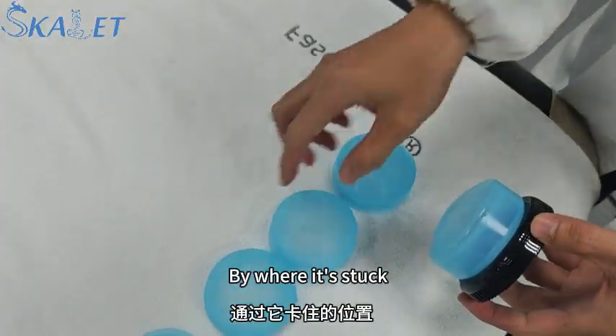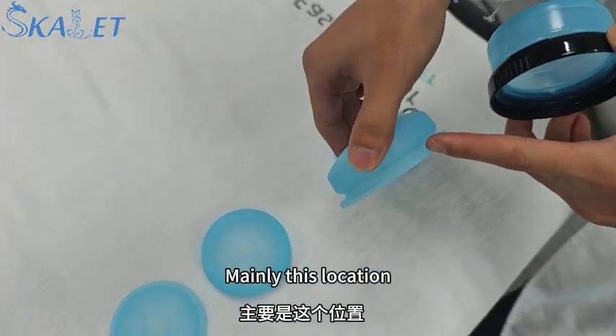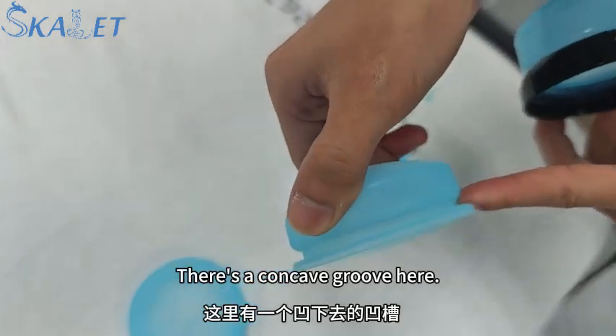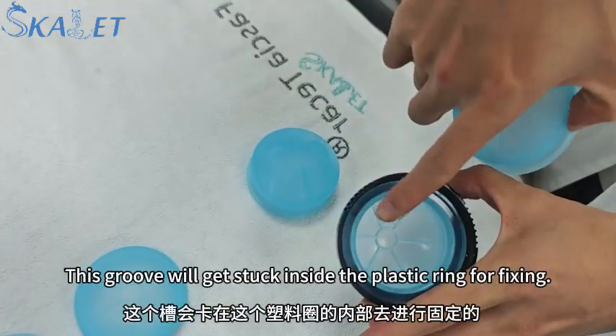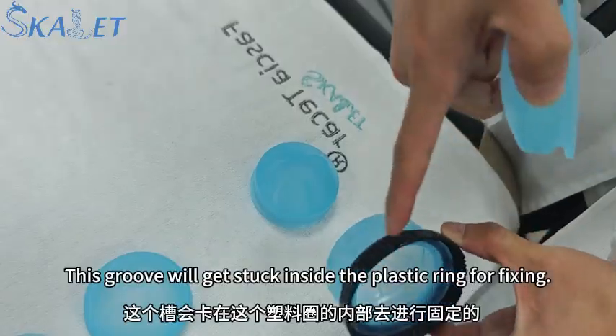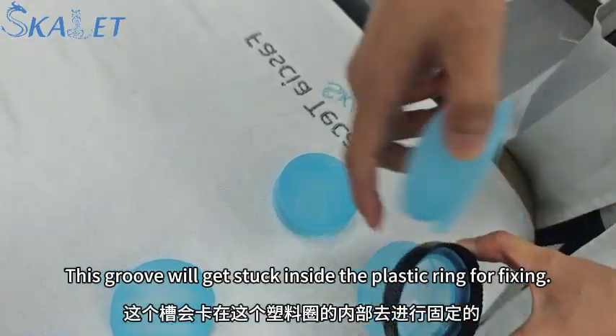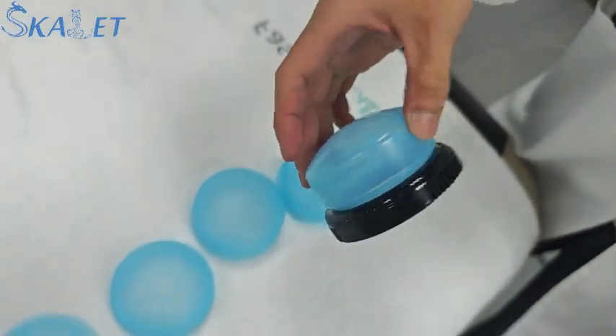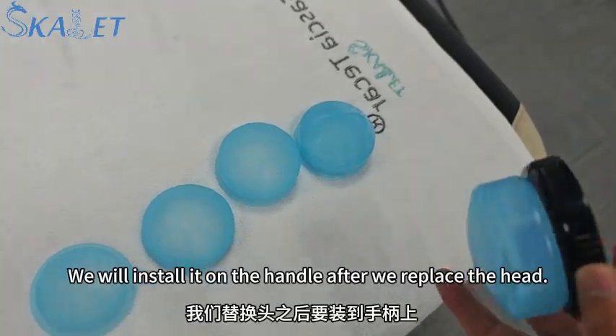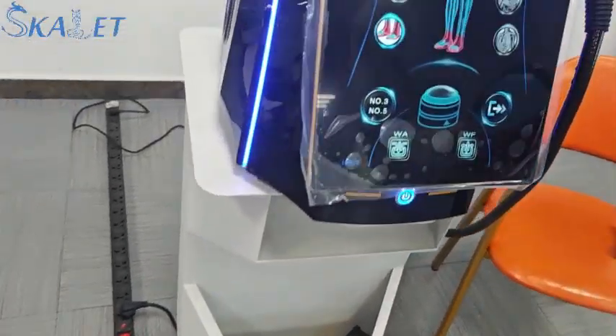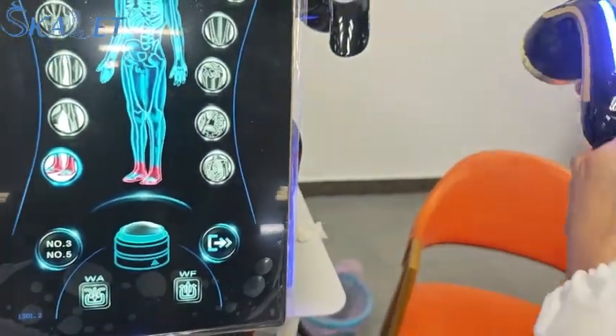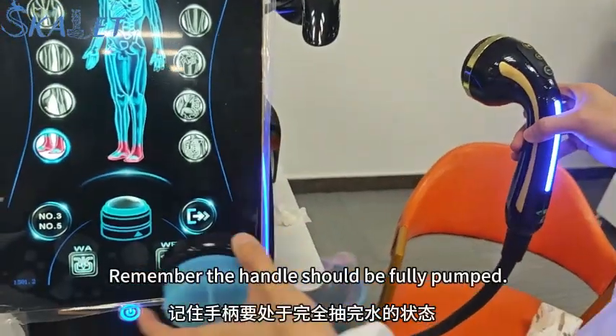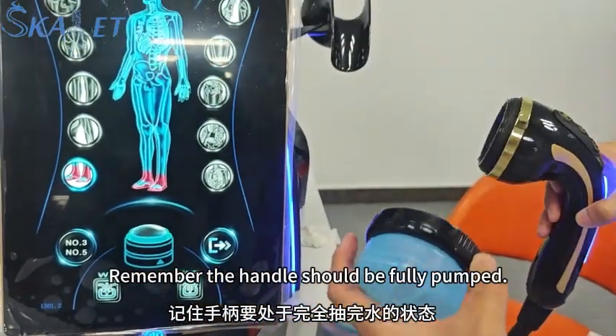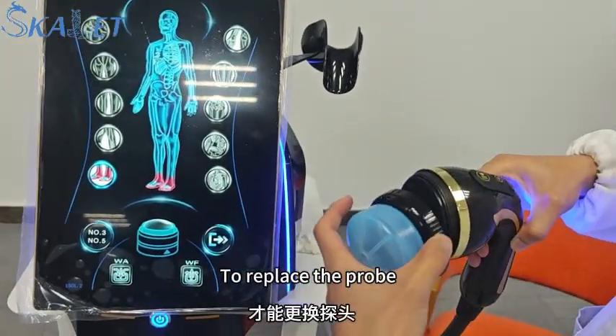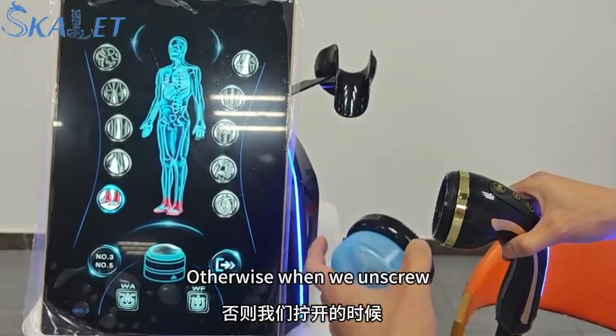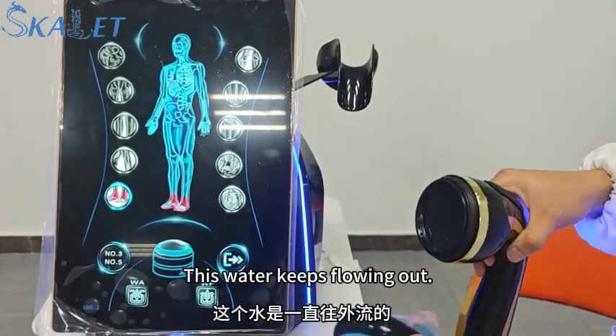By where it's stuck? Mainly this location. There's a concave groove here. This groove will get stuck inside the plastic ring for fixing. We will install it on the handle after we replace the head. Remember, the handle should be fully pumped to replace the probe. Otherwise, when we unscrew, this water keeps flowing out.